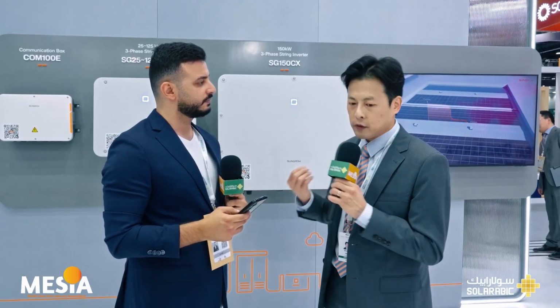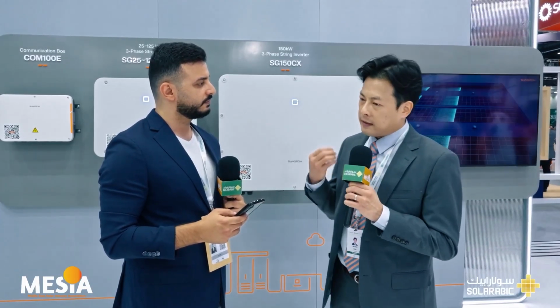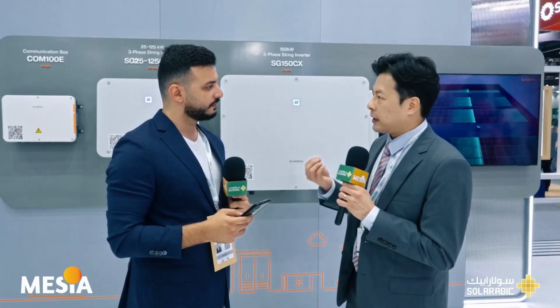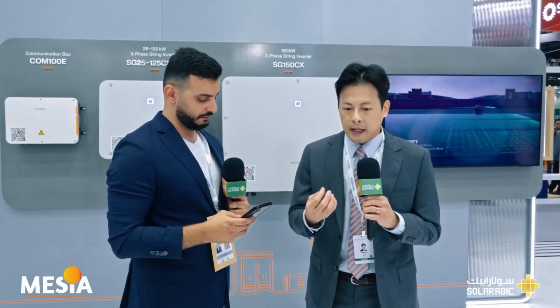The EMS energy management system analyzes the load profile and weather forecast upfront, then predicts the high load discharge at noon, the peak temperature period. It pre-cools the coolant fluid in the system, getting it ready for that peak hour, effectively increasing the effectiveness of the thermal inertia before the heat wave hits. Secondly, it has a smart mode switching technology.